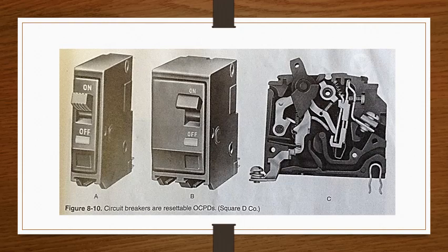The amperage rating of each circuit breaker must be matched to the circuit it protects. Information regarding finding the circuit's ampacity is found in Chapter 5, Conductors.